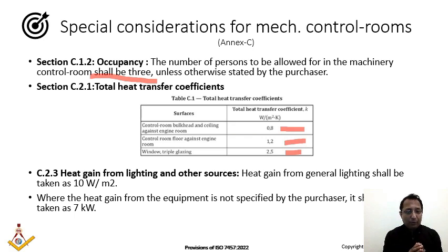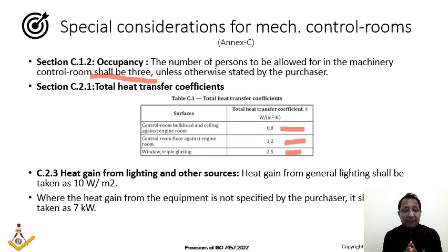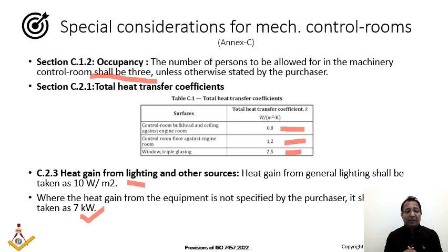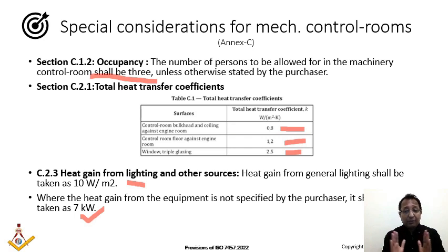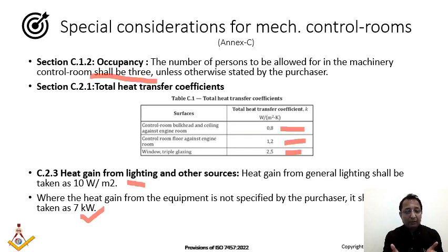Section C.2.3 covers heat gain from lighting and other sources in the machinery control room. Lighting heat gain can be taken as 10 W/m². Heat gain from equipment should be taken as 7 kW when vendor data is not yet available — this is specified in ISO 7547, so you can safely apply it in calculations and clearly document that 7 kW per ISO 7547 has been applied, avoiding delays while waiting for vendor input.